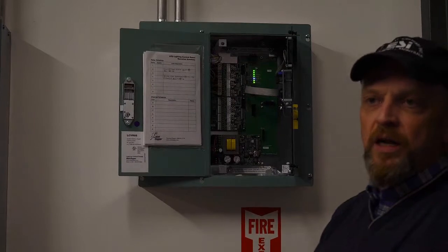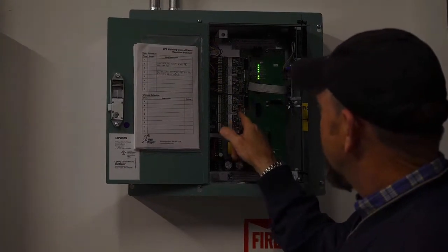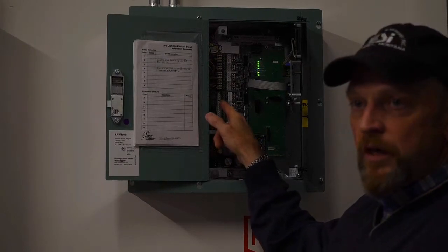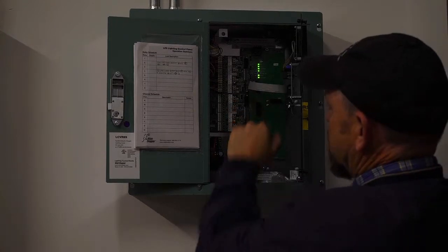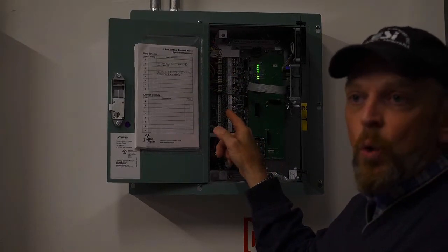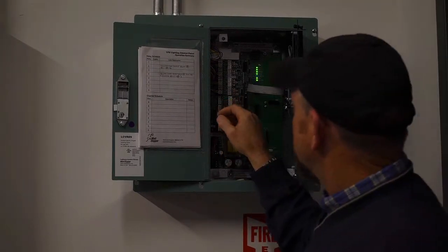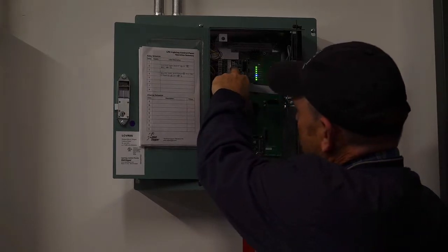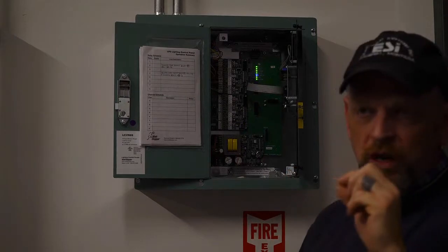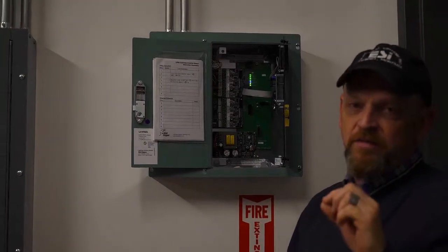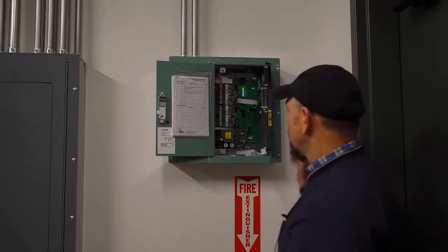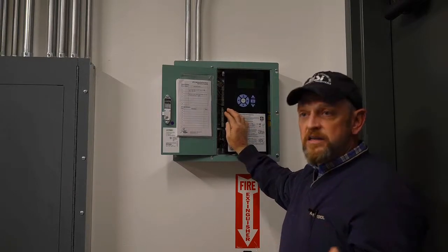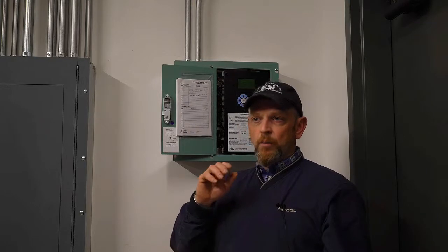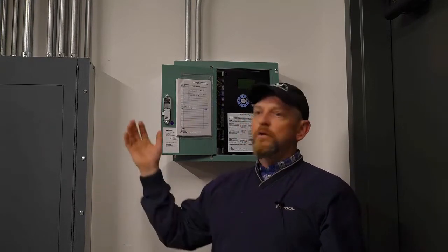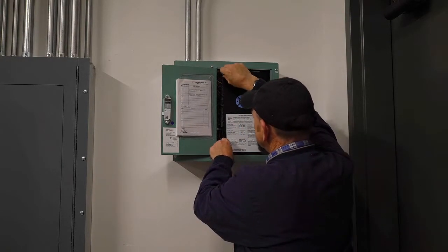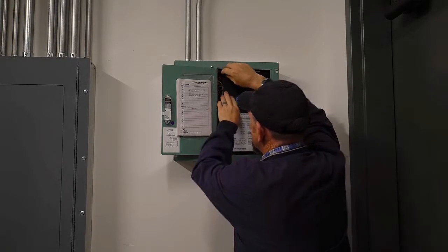If for some reason you need to manually turn lights on or off, you'll notice that there are little red buttons in here. You can see them. They're right there in a line. This system is set up so that it could hold more circuits than what you guys require. So what you'll see is that some are lit up, and you could touch that. Usually it's easier to use a little screwdriver or something just to tap that little red button, and that will activate that circuit on and off manually. Then it doesn't reset itself. So let's say you turned it off during the day. When it gets to dusk, it'll turn itself back on. Is that battery backed up? That is correct. These are off the inverter circuits.